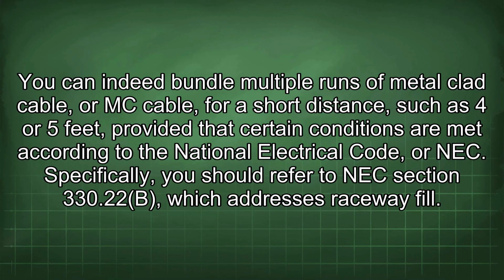You can indeed bundle multiple runs of metal-clad cable or MC cable for a short distance, such as 4 or 5 feet, provided that certain conditions are met according to the National Electrical Code, or NEC. Specifically, you should refer to NEC Section 330.22b, which addresses raceway fill.